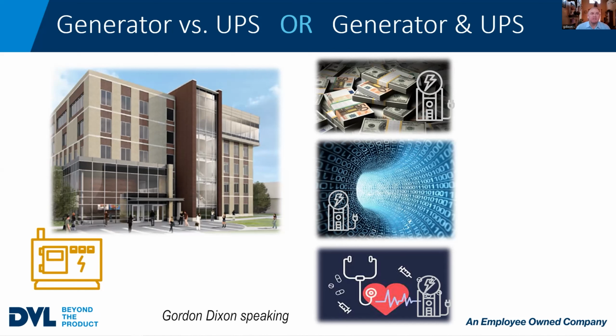Generally speaking, a generator is required for longer-term backup power, but there's going to be a gap, and a UPS is used to fill that gap before the generator comes on. If you've got a smaller facility with no need for a generator, you might go with just a couple hours of backup and a plan using only the UPS. But primarily, a lot of applications these days use both. The generator comes on, and the UPS carries the load during the transition before the generator accepts the power. So that's the overview, and we'll get into more specifics as we go.